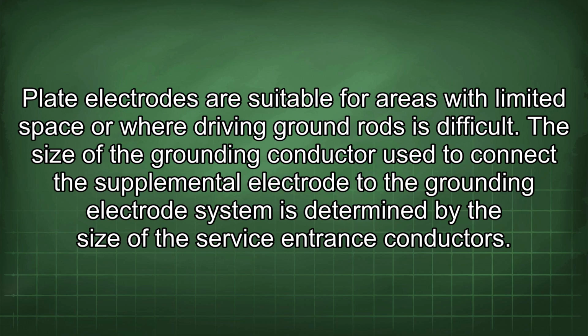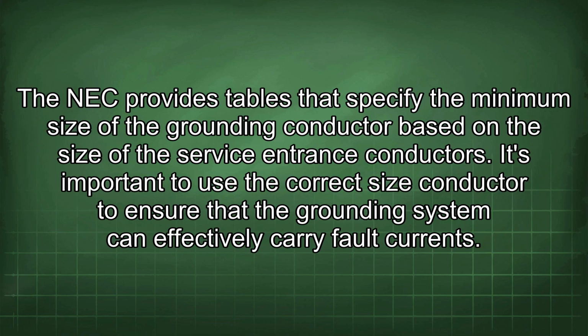The size of the grounding conductor used to connect the supplemental electrode to the grounding electrode system is determined by the size of the service entrance conductors. The NEC provides tables that specify the minimum size of the grounding conductor based on the size of the service entrance conductors. It's important to use the correct size conductor to ensure that the grounding system can effectively carry fault currents.